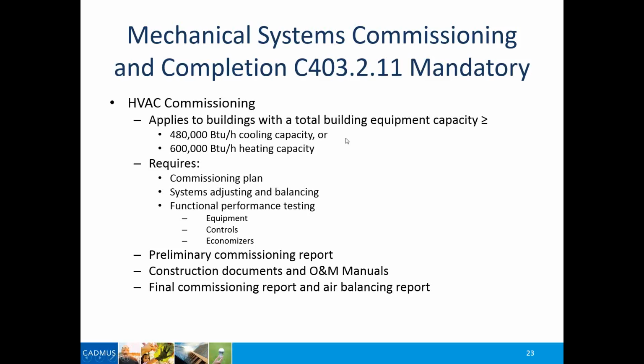So again, if I have a space in a strip shopping center, maybe a 5,000 or 6,000 square foot space or a 3,000 square foot space, and it's being handled by a couple of small packaged AC units on the roof, I'm not going to worry about this. But if I have a larger building with 480,000 BTU per hour cooling capacity, it does kick in the commissioning requirements, because right now we're getting a lot of our energy savings with mechanical controls. And we've kind of maxed out on equipment efficiency to an extent.